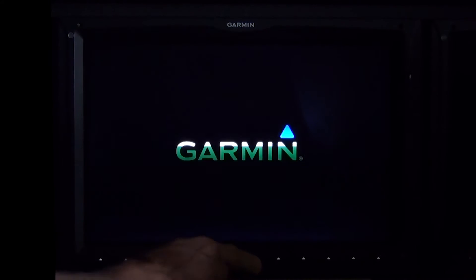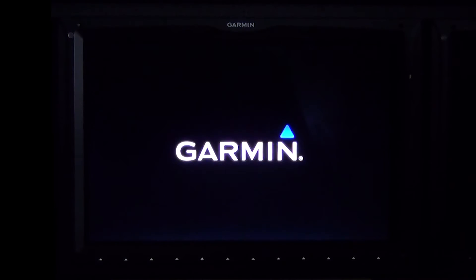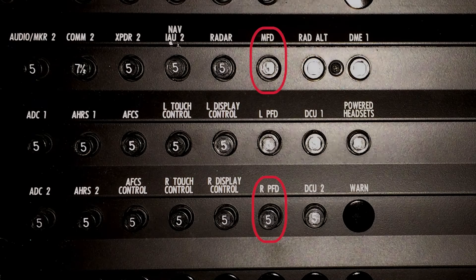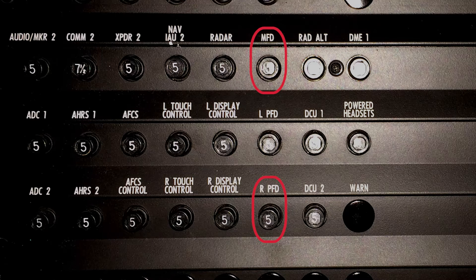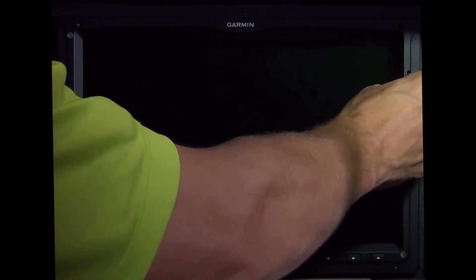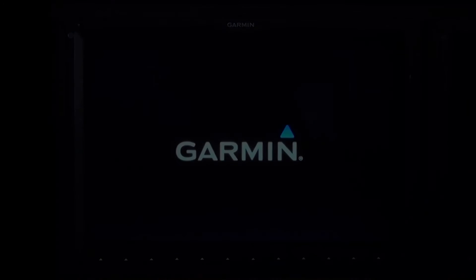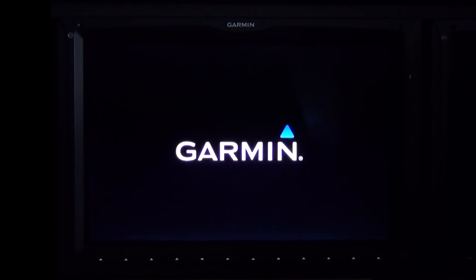This process must be completed on the MFD and the PFD2. The circuit breakers previously pulled for the MFD and PFD2 must be engaged when the NavData card is placed in the display. When the last update is complete on PFD2, select Power Off. Remove the NavData card from the PFD2 and place it in a secure location in the aircraft. Select Power On.